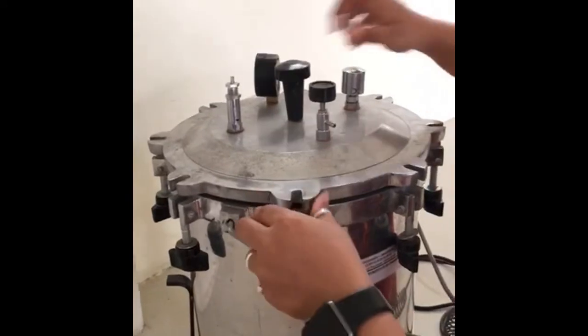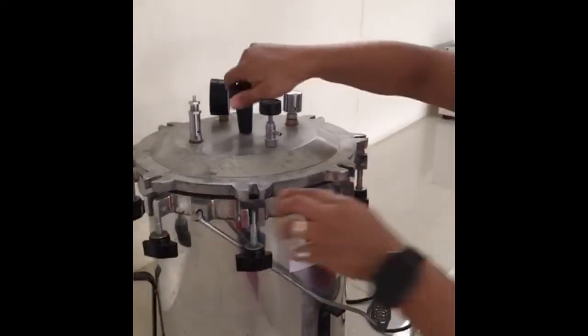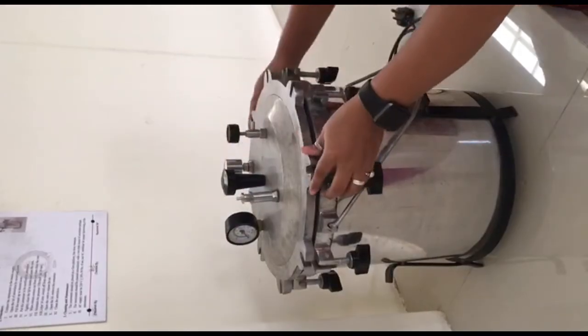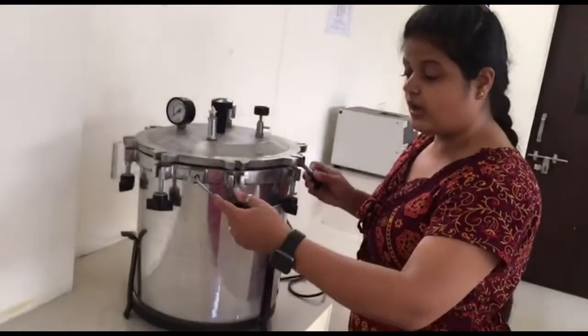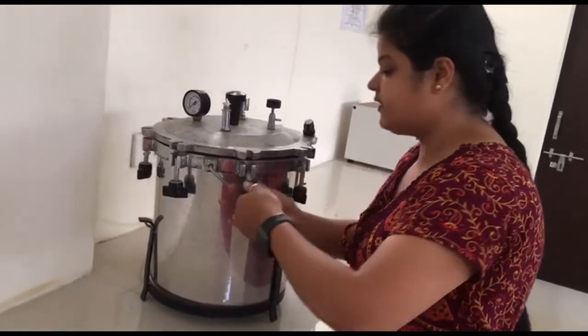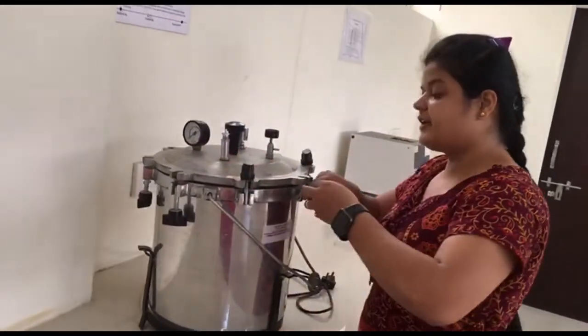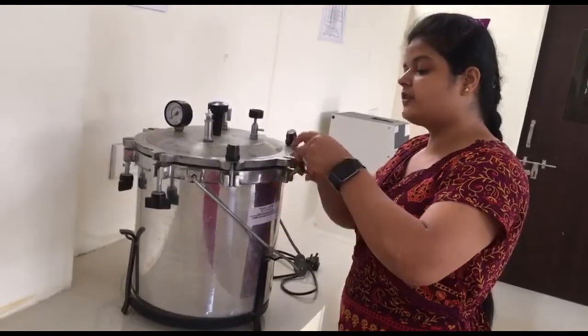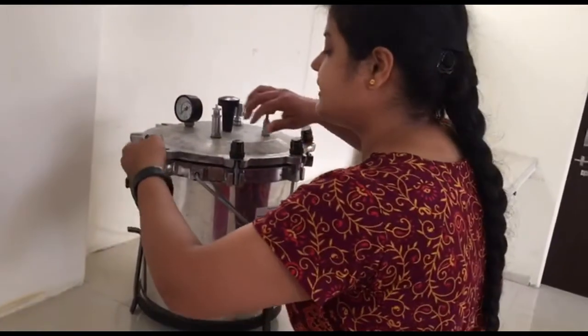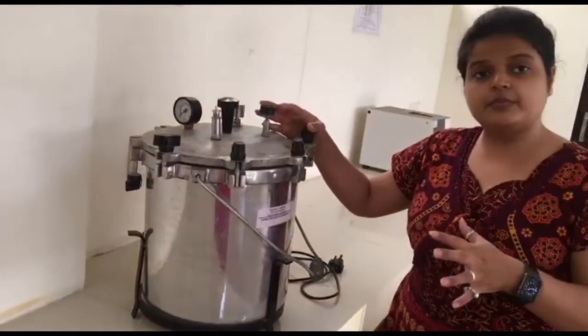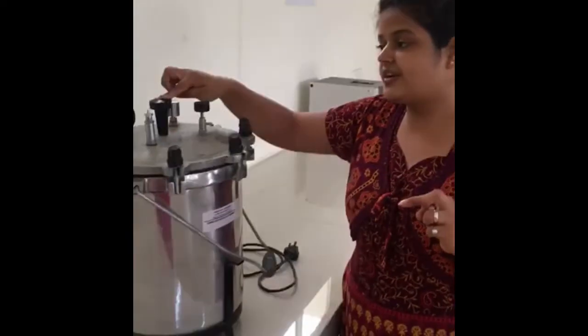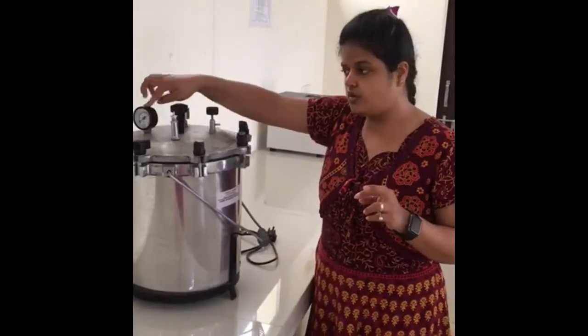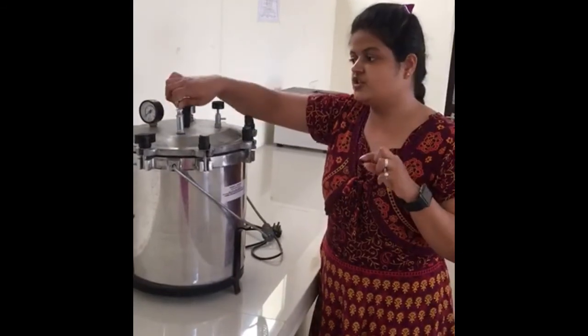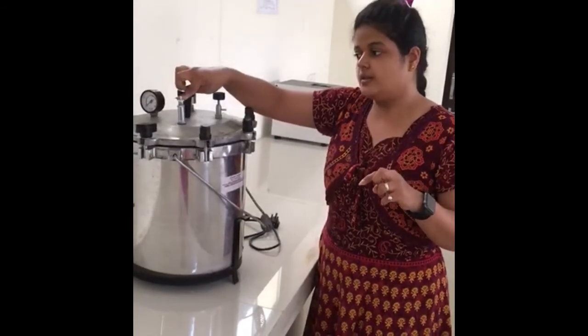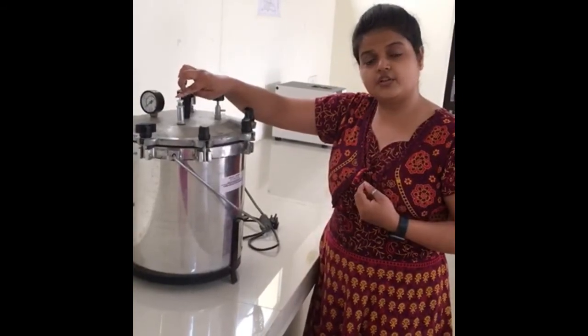Okay, so one thing you need to keep in mind is that whenever you close the autoclave, make sure that the lid of the autoclave is properly adjusted. Then only you have to screw the autoclave lid. Whenever you perform any practical, before starting, make sure that once again, before switching on your autoclave, you check all the parameters. You check the pressure valve, you check the vent or whistle, you check the safety valve. The safety valve is there for the prevention of destruction.